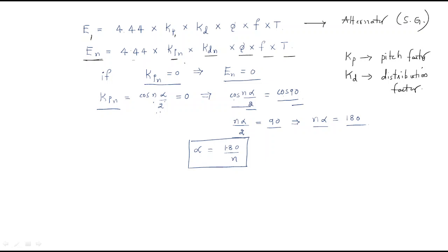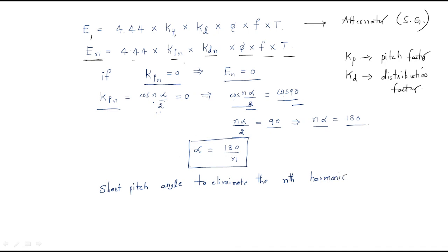Therefore α = 180°/n. This is called the short pitch angle required to eliminate the nth harmonic. For example, to remove the 5th harmonic, the short pitch angle α = 180°/5 = 36 degrees.